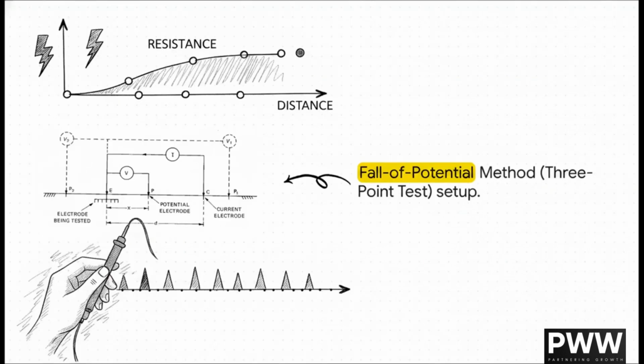All right, Section 3, Earth Resistance Measurement Techniques. Let's fast forward a bit. The grid is physically in the ground, and it is commissioning time. The fall of potential method, also known as the 3-point test, is the gold standard here. You pass a current between the earth electrode you're testing and a remote temporary current spike. Then, you use a third potential spike placed somewhere between them to measure the voltage drop. By moving that potential spike away from the test electrode in measured steps, you can literally plot a curve of apparent resistance.